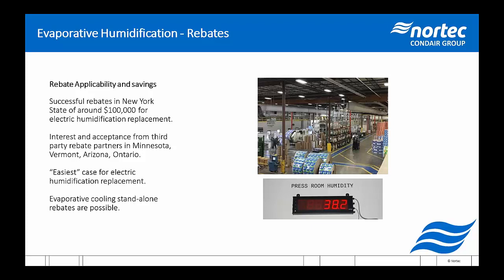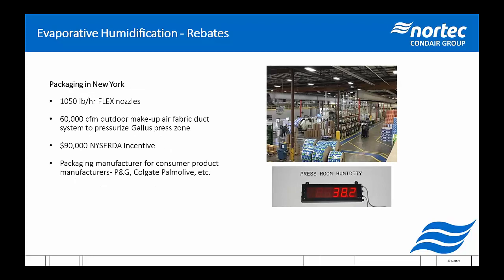If there's an electric humidifier in the building with a relatively high load or relatively large usage case, we'll be looking at a fairly easy case for rebate there. That being said, we can absolutely apply for rebates with evaporative cooling standalone products, or even replacing a compressed air system, because compressors are one of the things utilities like to target to get them off the grid. So in this job specifically, it was about 1,000 pounds an hour of humidity, and they were doing that before with electric humidification. It was 60,000 CFM outdoor air, and they replaced it with in-space humidification. So it was about $90,000 for this one, and this is not the only one we've done in the area.